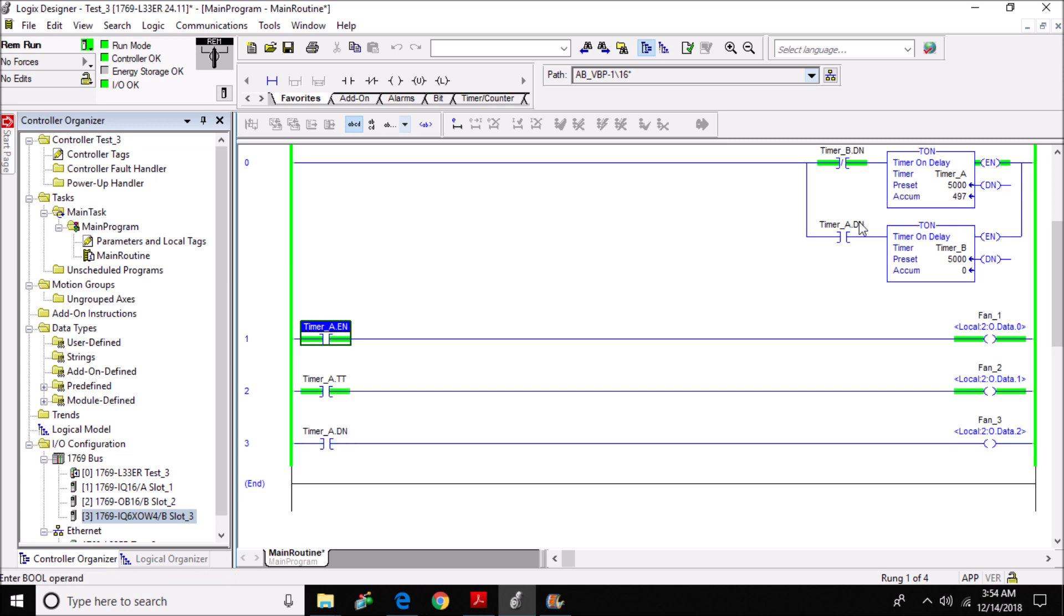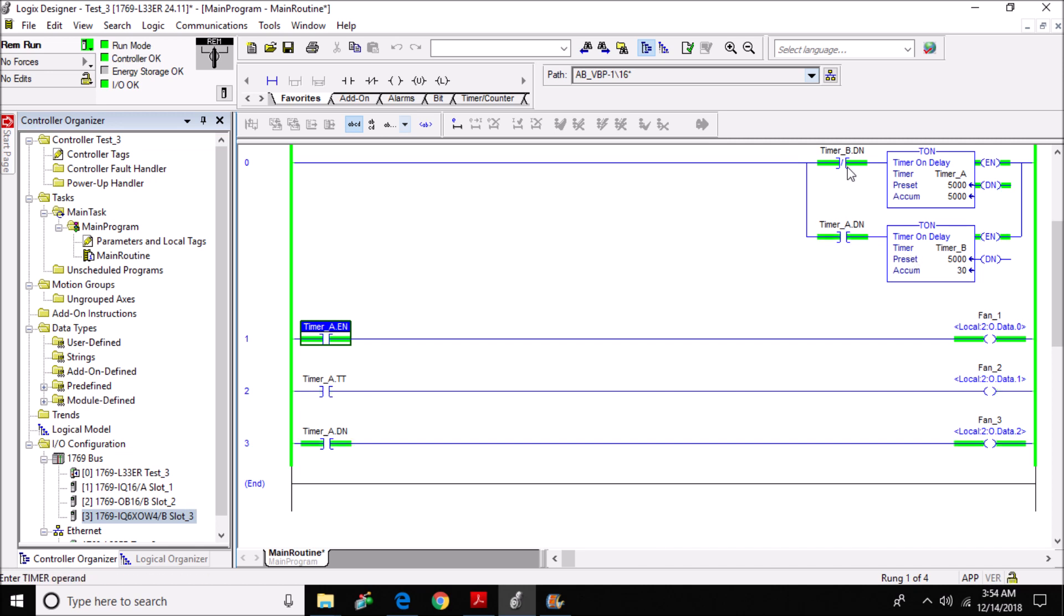Once the accumulated time here is equal to or greater than the preset, it will trigger the done bit for timer_B and it will begin to accumulate time until it meets its preset. And once the preset is met here, it will trigger the done bit here, which will reset this timer back to zero and resets the done bit here, which resets this timer.